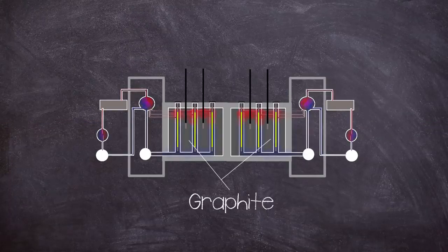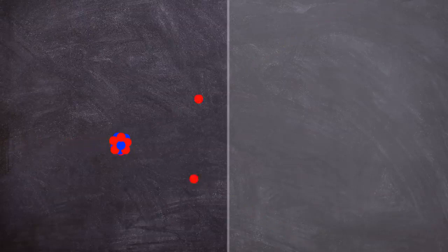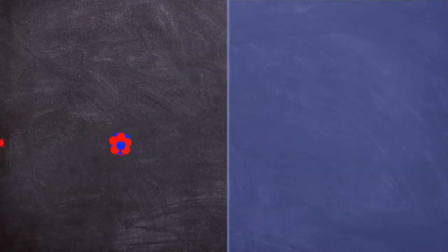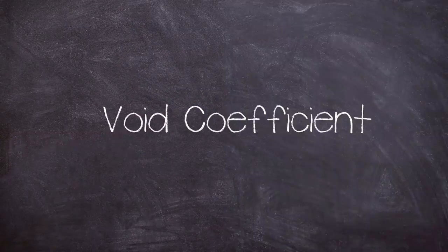As mentioned, the reactor employed graphite blocks for its moderator. A moderator is used to reduce the speed of fast neutrons released from fission so they can better facilitate a chain reaction, getting more use out of the fuel. Ideally moderators work without capturing neutrons, leaving them as thermal neutrons. But the design has its potential flaw in having a separate coolant that can also absorb neutrons, which can make the reactor unstable in certain situations. This brings up the big elephant in the room: void coefficient.